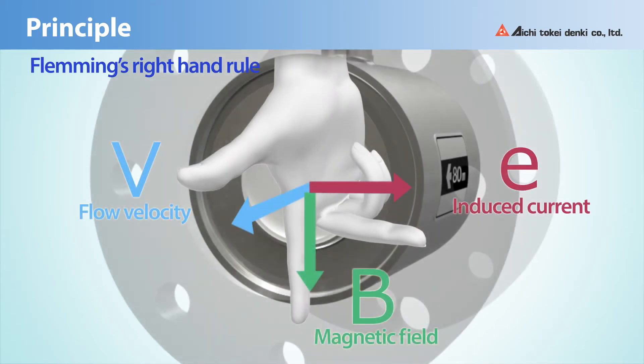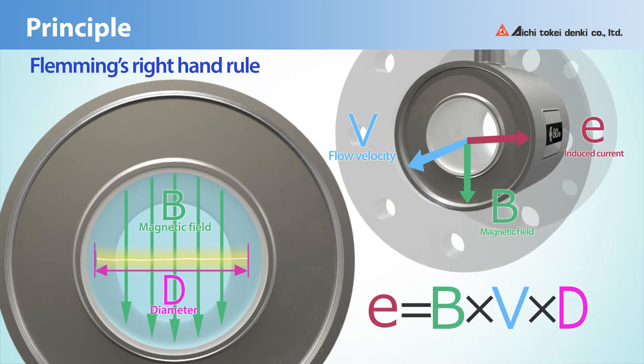The measurement principle of SU is Fleming's right-hand rule. The mechanism involves the magnetic field that is generated inside the meter. And as the water passes, some electric potential is generated in proportion to the water flow. Then the meter calculates the volume of water by catching the potential with its electrodes.